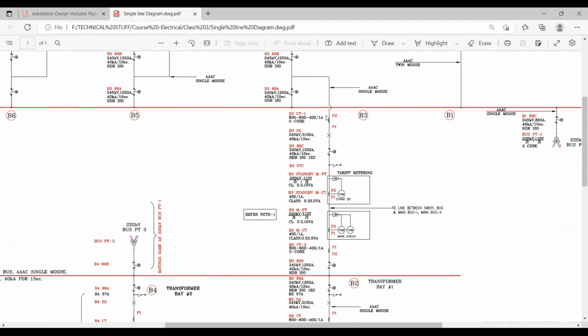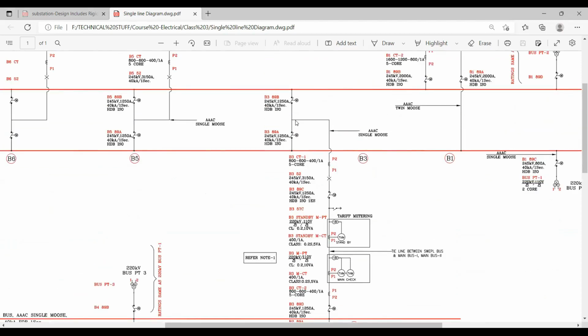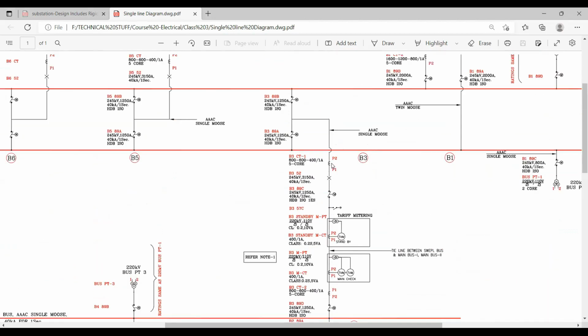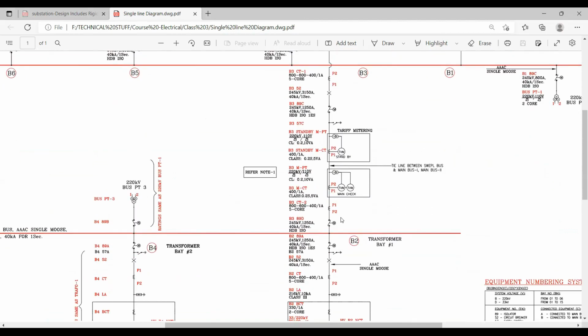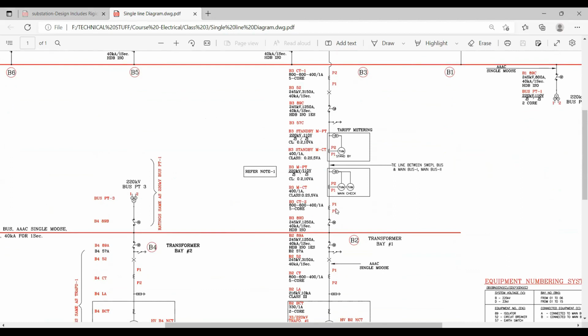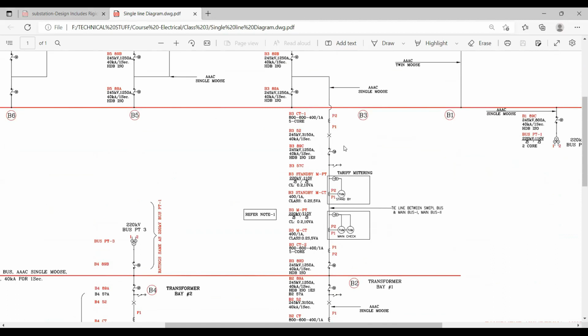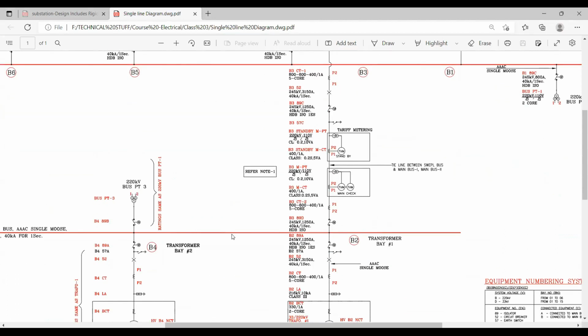And if you see here, I said that this P2 is connecting to this P1. But what I said was, P1 should be here, P2 should be here. And for this CT, P1, P2 should be here, P1 should be here. Why is it different? Because I am protecting this bus from this CT. I will clear this in the protection chapter, team. So this bus bar is protected by this CT, and the upper side of the bus bar is protected by this CT. So the total zone is covered here.